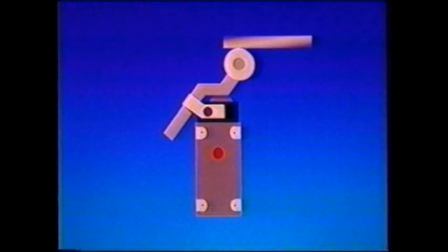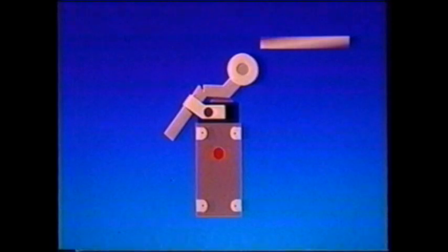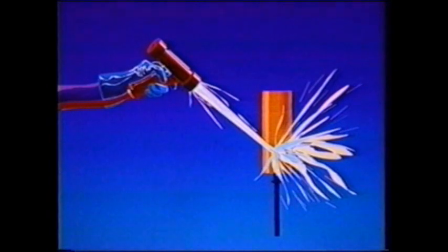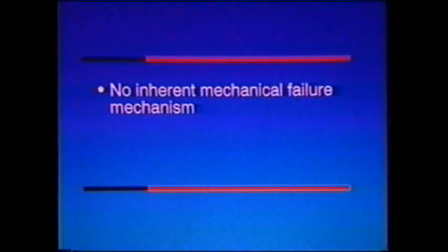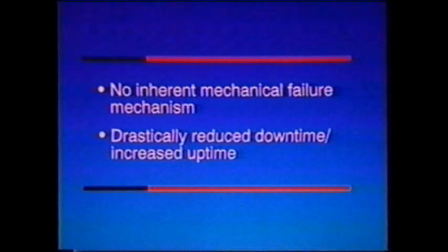Mechanical switches are high maintenance devices. Actuators stick, break, and wear, and mechanical contacts have finite life expectancies. However, proximity switches are completely solid state devices. There are no contacts to wear and bounce. Proximity switches provide non-contact sensing, so there are no actuators to wear, break, or get out of alignment. And because there is no actuator shaft, proximity switches can be sealed against harsh environments. Proximity switches have no mechanical components, so they can reduce downtime and increase productivity.